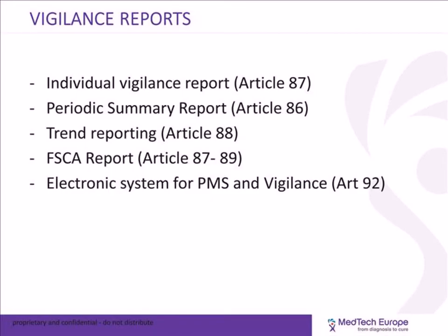Also, and even if this is not the specific focus point of this presentation, we need to mention vigilance as well. Vigilance is part of the post-market surveillance, and the collection and reporting of adverse events and eventual filing to the authority still exist under the MDR, with some notable modifications. So we need to note that the filing of reports has been modified. Instead of filing an adverse event report to the country where the event occurred, the filing will be done now to the central EUDAMED, which is a major change.